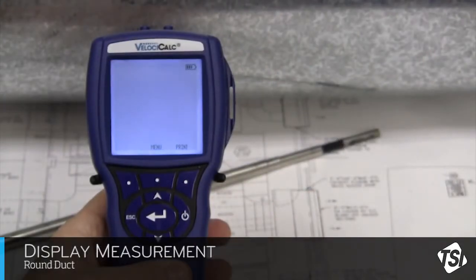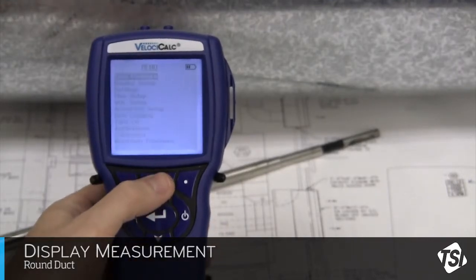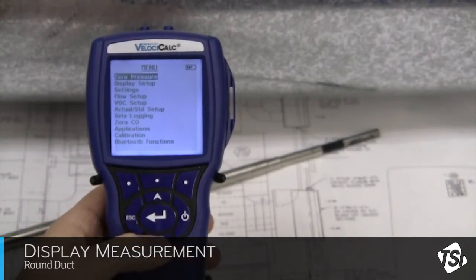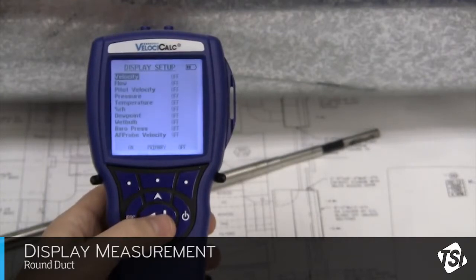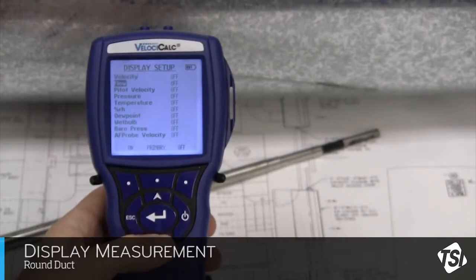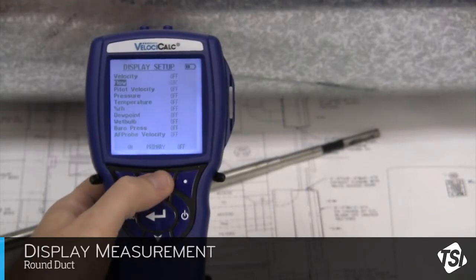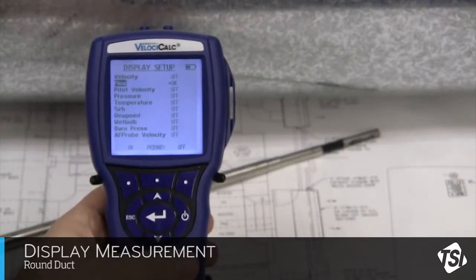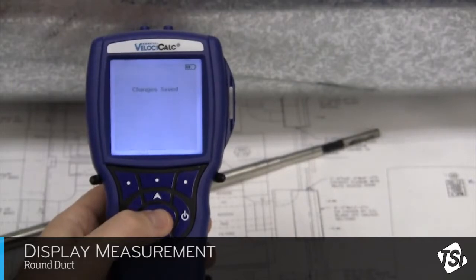The first thing I need to do is make sure the screen will be displaying the measurement I'm interested in, airflow. To select what measurements will appear on the display, click on Menu using the middle soft key. Arrow down to Display Setup and press Enter to open this menu. In this case, I will make sure that Flow is highlighted and press the middle soft key to make this my primary measurement. Press Enter to save these changes and we'll be back at the main menu.